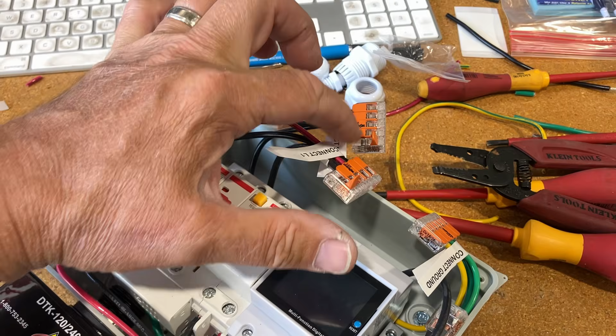Now, let's follow the wiring here. Once you give it power, we have one line going to the top of our circuit breaker on both. Boom, boom, just like that. You see that? Now, on the other ones, because this is a 5-conductor WAGO, one goes to our surge protector on each. One goes to our power monitor on each. So that's the 3 wires. There's 2 extra spots there, so you'll just use one more to connect L1, L2. Now, on the protected side of our circuit breaker, which is rated for 63 amps, we have one wire going here through the amp reading and then going to this WAGO connector, which is going to our load. On the other side of the circuit breaker, that's going directly to our load.